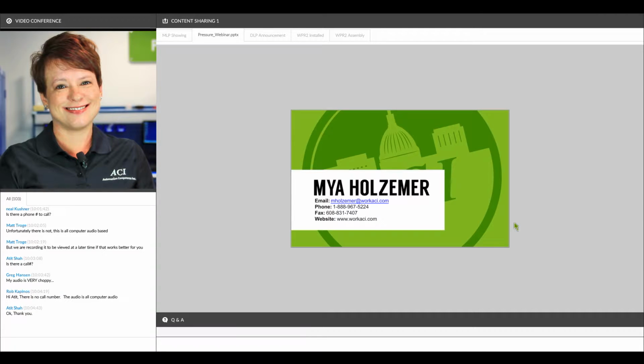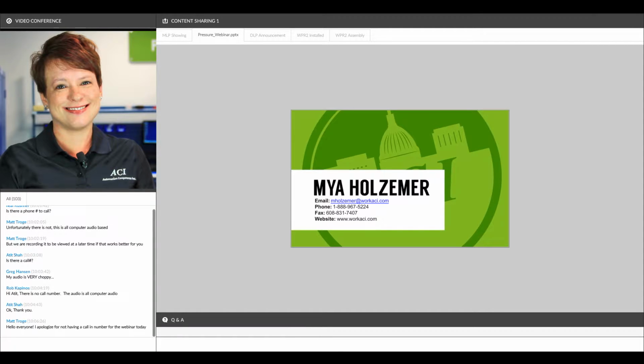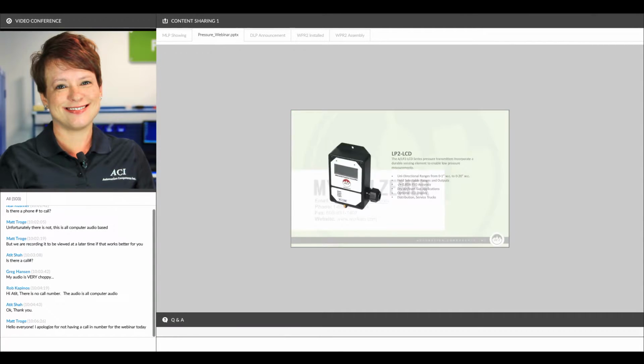ACI makes products for both dry air and inert gas applications, as well as wet and other harsh media applications. And today I'd like to start out with the products that we have for dry air and inert gas needs, beginning with our LP2. The LP2 is a unidirectional or positive pressure transducer. It's good for pressure ranges from 0 to 1 inch of water column up to 0 to 20 inches of water column. And output selections are 1 to 5 volts, 2 to 10 volts, or 4 to 20 milliamps. It is field selectable, so you get pressure ranges and outputs in each version.